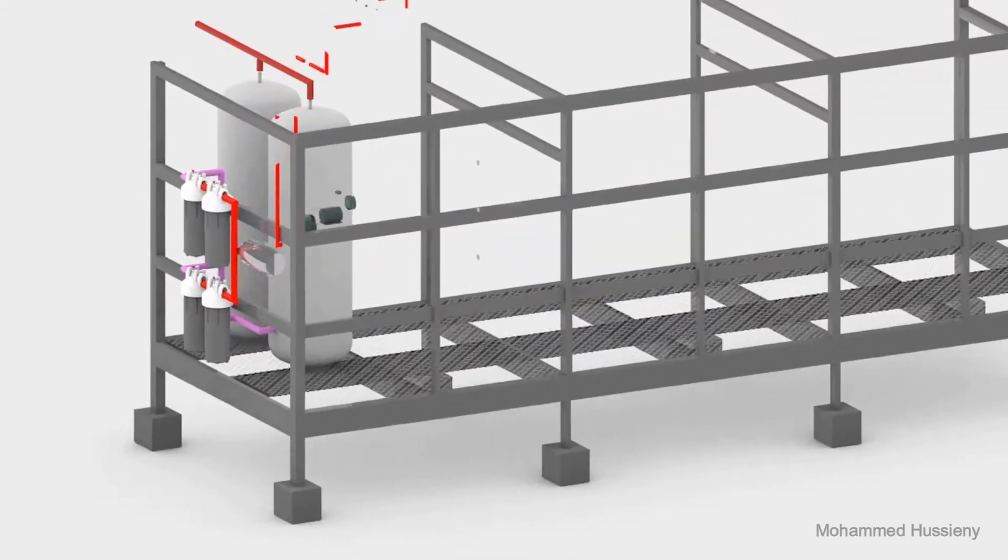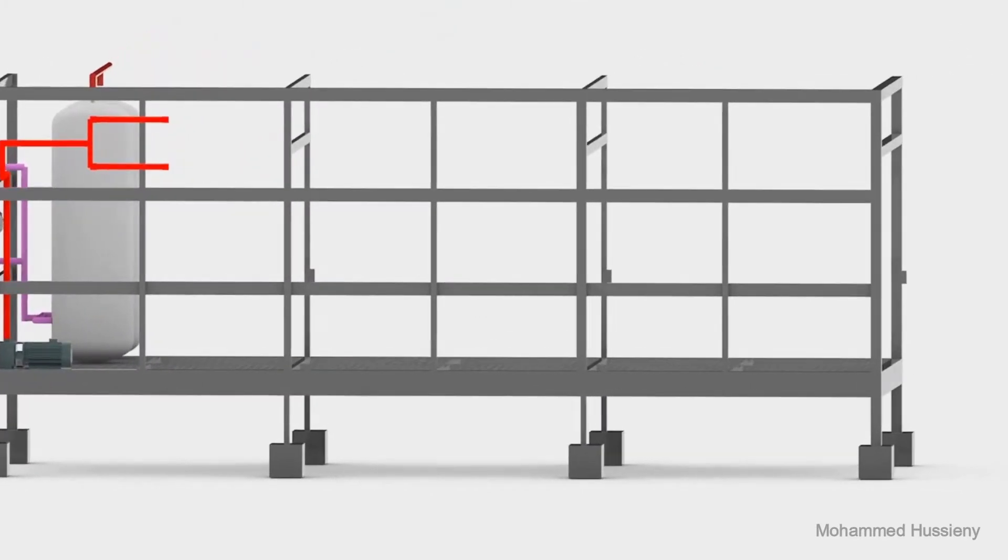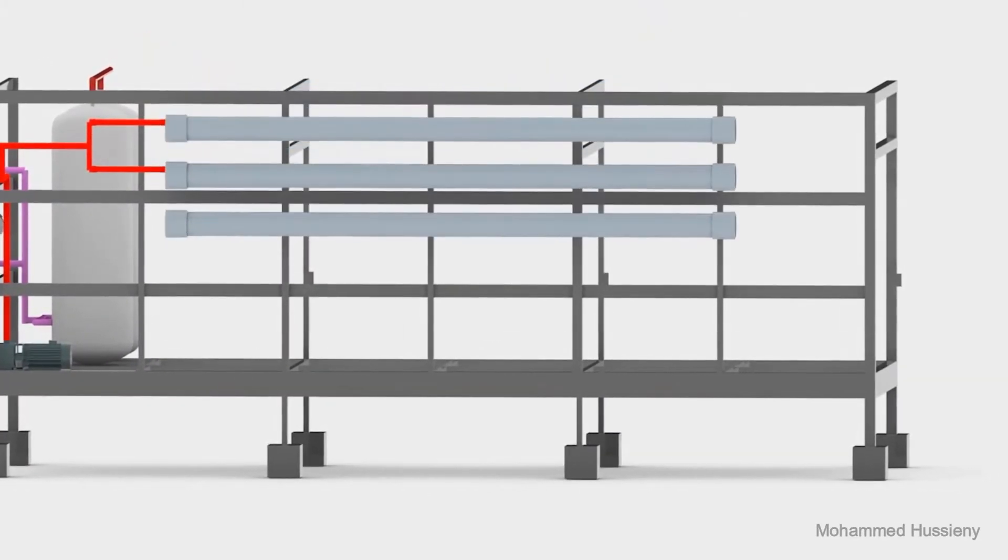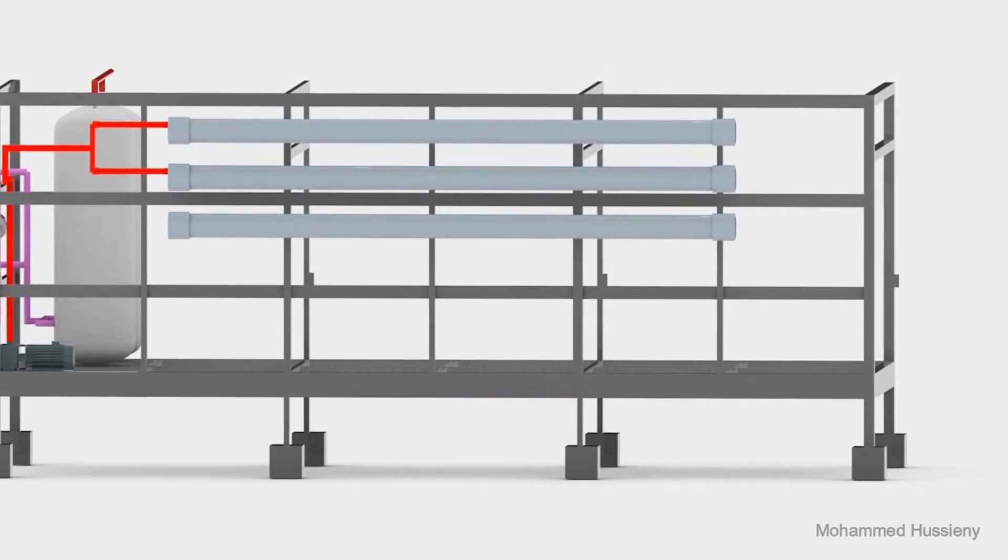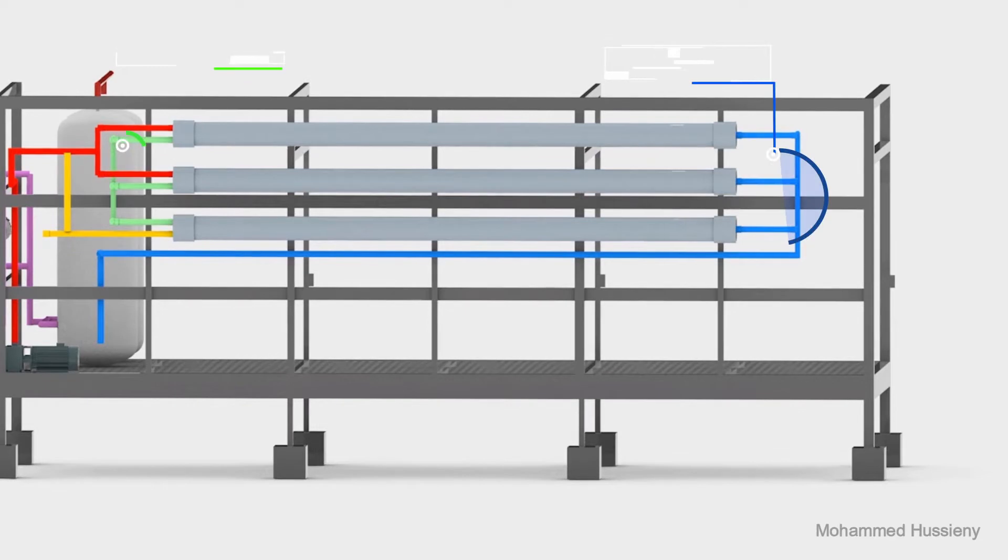Now, the water is ready to get pumped into the RO system to remove the main part of the dissolved salts. The flowing water gets pumped into the first stage of the first pass. Then its concentrate flow enters the second stage of the first pass to increase the overall recovery percentage.